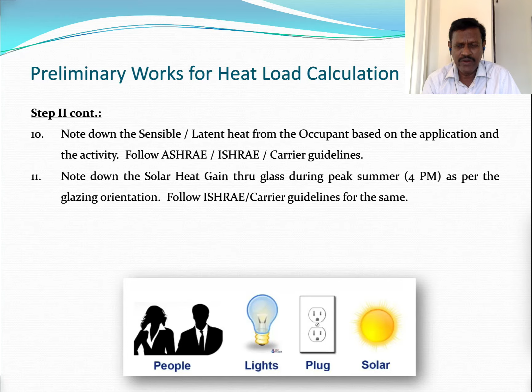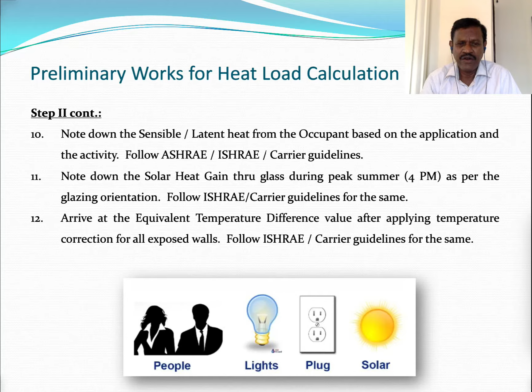For the solar heat gain, based on the glazing area, you have to consider 4 pm as the peak load, and all your calculation has to be based on 4 pm. Then for the wall heat gain, you have to work out from ASHRAE or Carrier guidelines the equivalent temperature difference for the exposed wall, and note down all that information in your load calculation sheet.